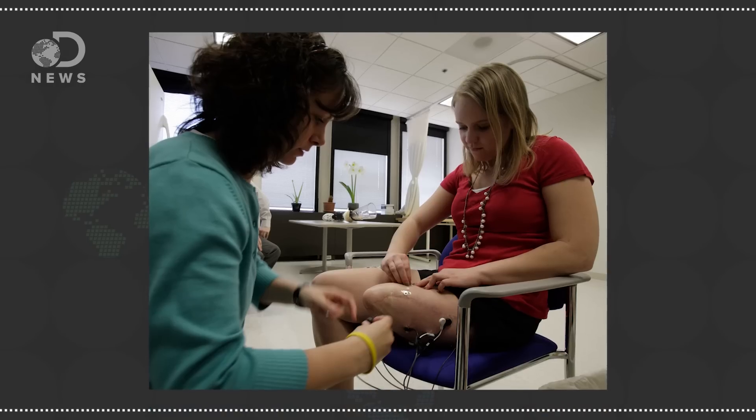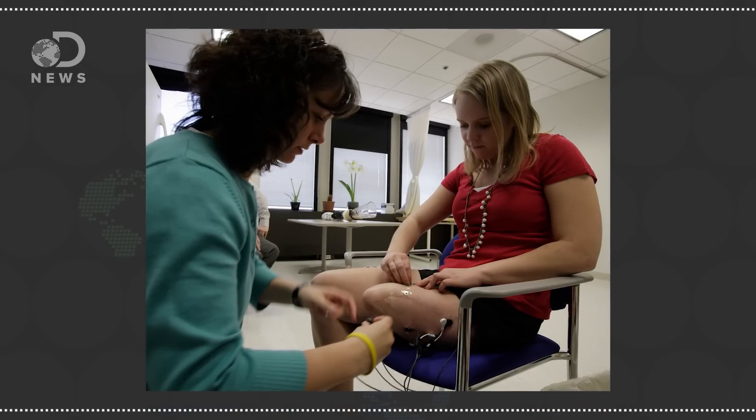While fit and materials get progressively more advanced, so does the technology. Most new robotic limbs are myoelectric controlled, meaning muscles in the remaining limb naturally create electrical signals that are picked up by electrodes in the prosthetic. For the past few decades, medical technology allowed patients to control their device through electrodes placed on the skin. But that's an imperfect design — moving or sweating might dislodge the electrodes.